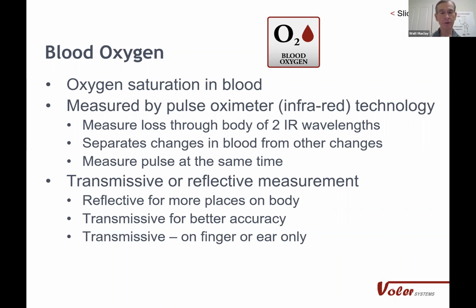And I mentioned you've got the transmissive type and the reflective type, where the reflective is the one people want to use because it's convenient. It works almost everywhere, except not so well on the wrist because there's not so much blood there. It takes quite a bit more work to get the reflective type to work because the signal is small. So you have a lot of noise and a small signal, which if you're an electrical engineer, you know that's a difficult thing to overcome, but there's lots of algorithms dealing with signal to noise ratio, so it can be done. But the transmissive only works on the finger and the ear, where you can send infrared light through the body.